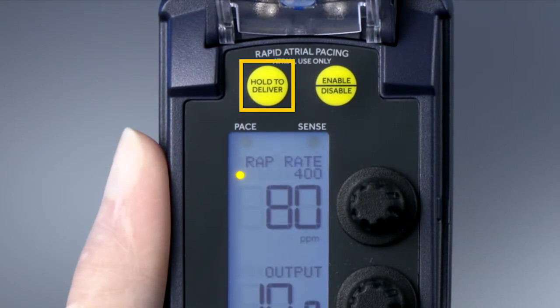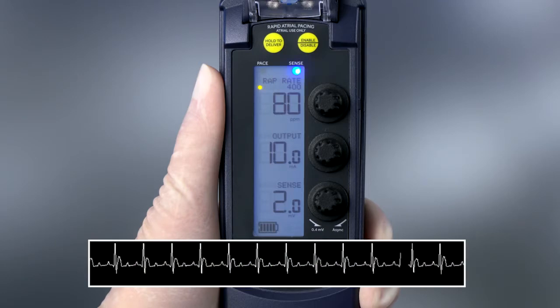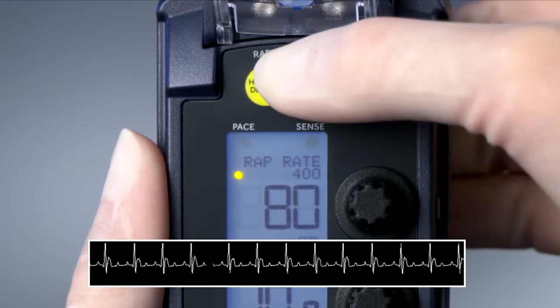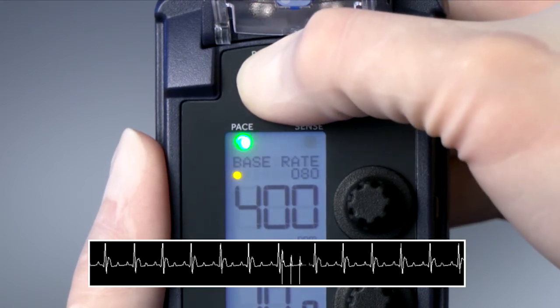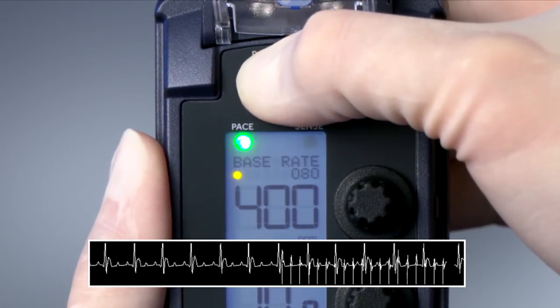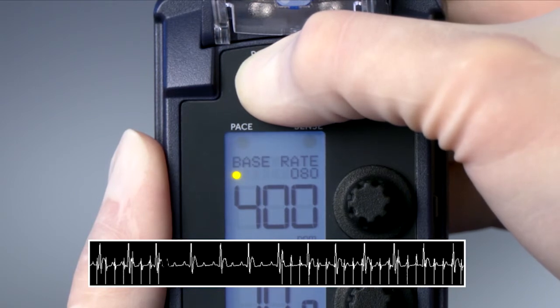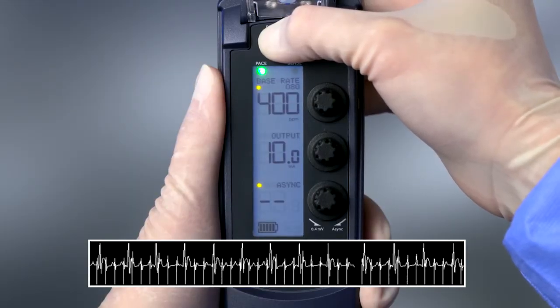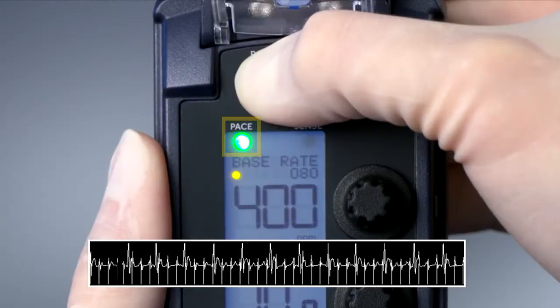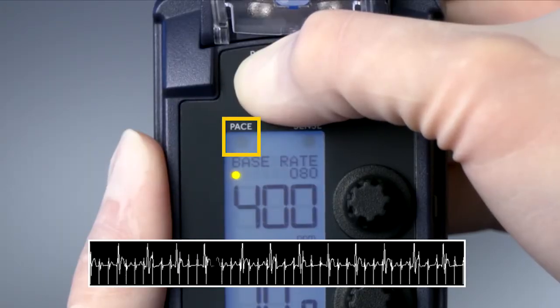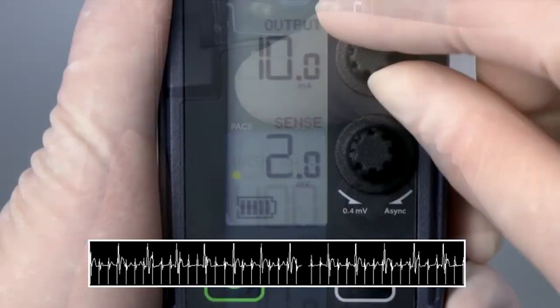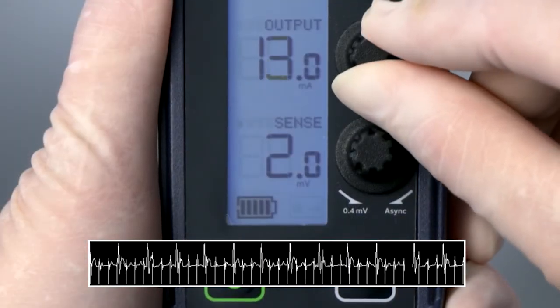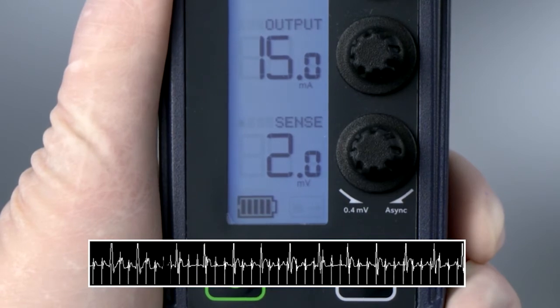Press and hold the Hold to Deliver button to deliver Rapid Atrial Pacing. During delivery, the previously set pacing rate and the RAP rate will switch places — the RAP rate will be in the larger text field until RAP delivery is finished. AOO pacing begins at the displayed RAP rate and current atrial output. The Pace LED flashes during delivery of RAP pulses. The pacing rate and output can be adjusted while delivering Rapid Atrial Pacing.